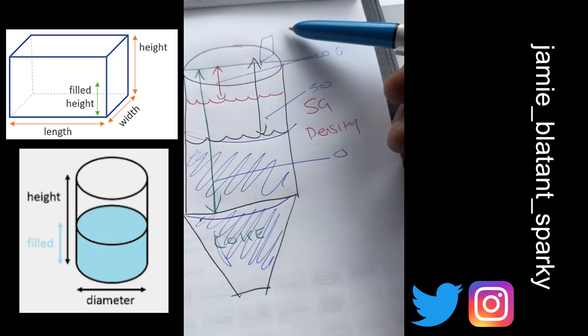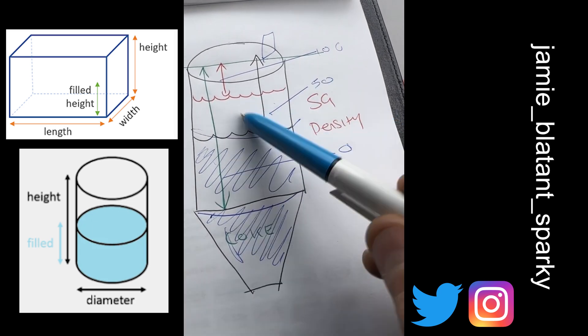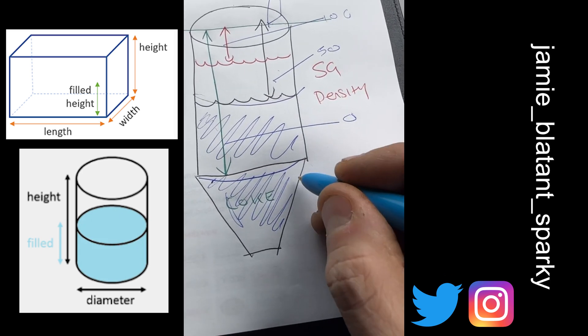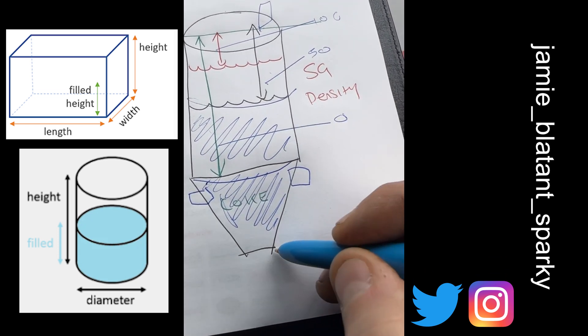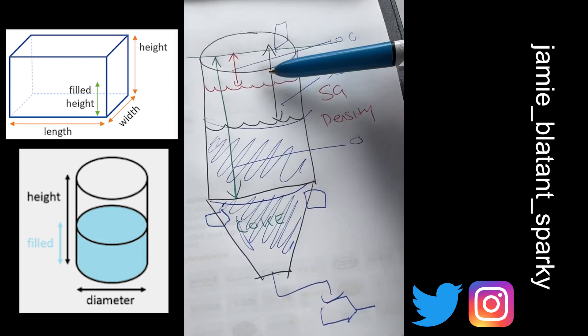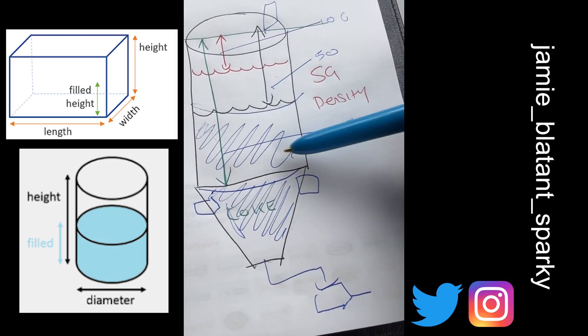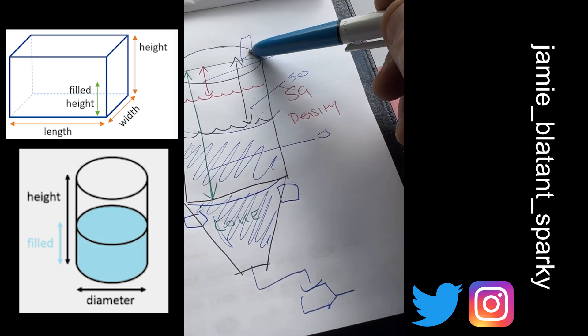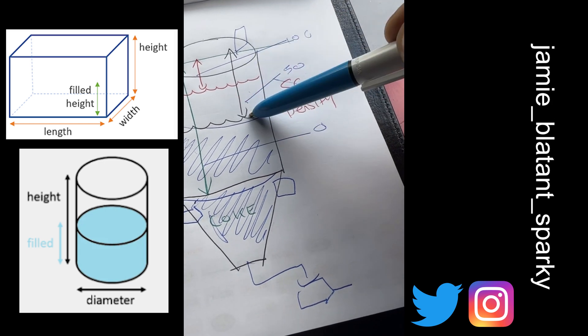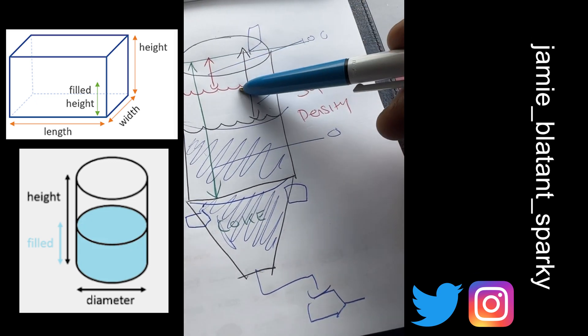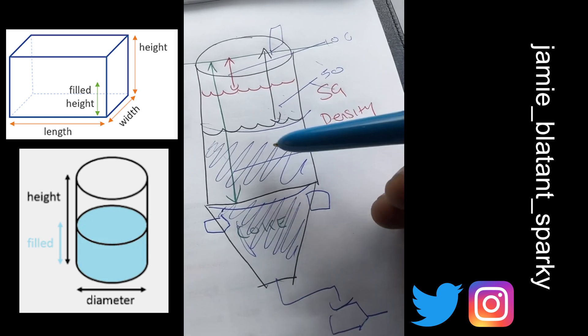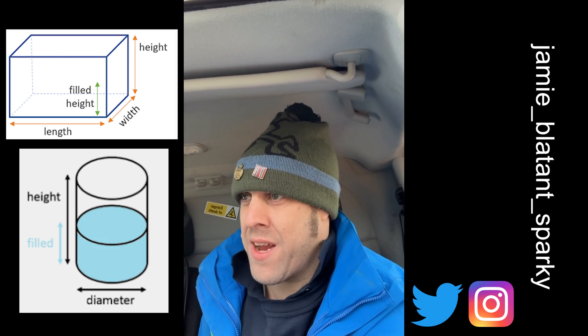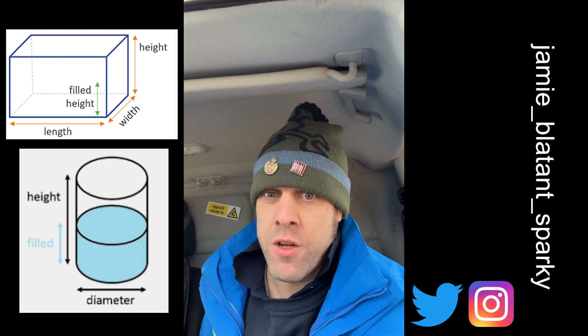Use that to calibrate whatever measuring device you put in the top. You can always trust the mass if you check it. For anything you want to coarsely weigh — sand, cement, sugar, flour — this is a great method. If you're making pharmaceutical products you'd put load cells on and weigh it precisely, then check-weigh it in a smaller weigher on the way out. For low-accuracy applications this mass calculation will always give you probably around five percent accuracy on your volume. If you don't trust what you've been given or don't trust the sensor, take the values — whether it's percentage, milliamps, or depth — and do the measuring yourself with a tape measure, then check whether it compares to your process value.